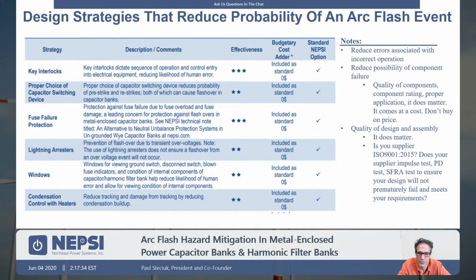If you purchase a metal-enclosed system and it doesn't have windows, at some point along the way, some maintenance person is going to say, okay, I want to get into this enclosure. Let me see what's going on here. He will open it while it's energized to check things out. That is an arc flash hazard, and we eliminate that by putting windows in our equipment.